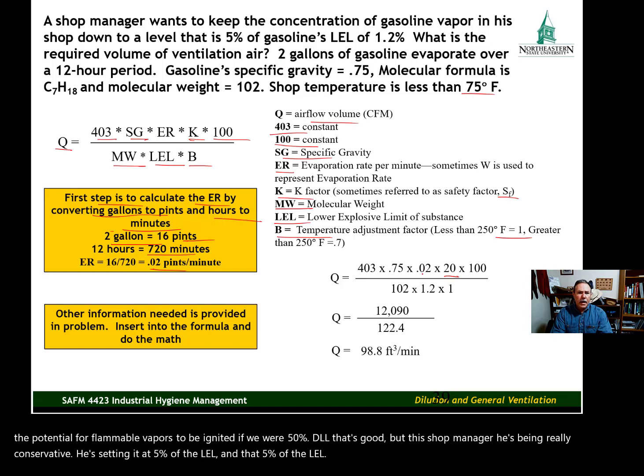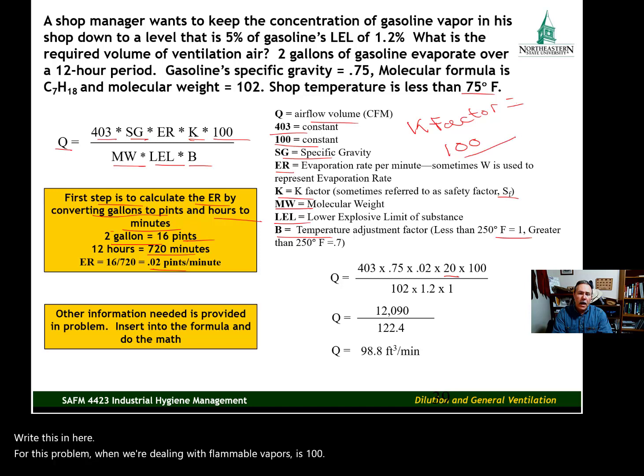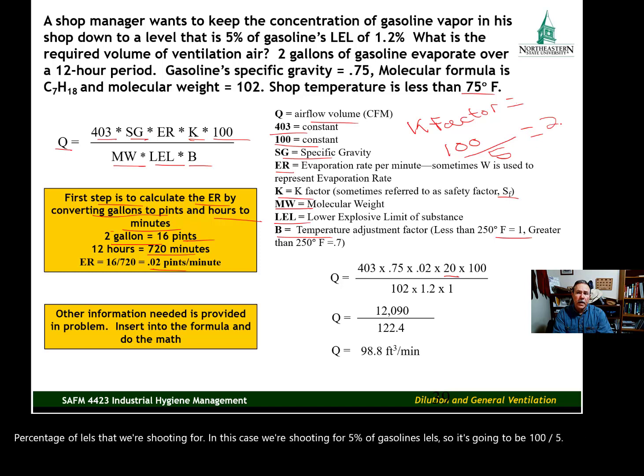That 5% of the LEL converts to a K factor of 20. I don't have that anywhere here on the formula, but the K factor for this problem when we're dealing with flammable vapors is 100 divided by the percentage of LEL that we're shooting for. In this case, we're shooting for 5% of gasoline's LEL, so it's going to be 100 divided by 5 equals 20.